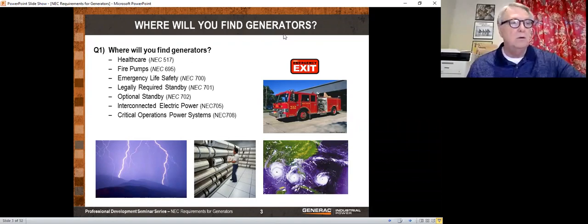Let's talk a little bit about where we find generators in the code. The NEC, of course, stands for National Electrical Code. NEC 517 is healthcare. There is some stuff in there on that. NEC 695 is fire pumps. The biggest sections are 700, 701, and 702. That's emergency, life safety, legally required, and optional standby.